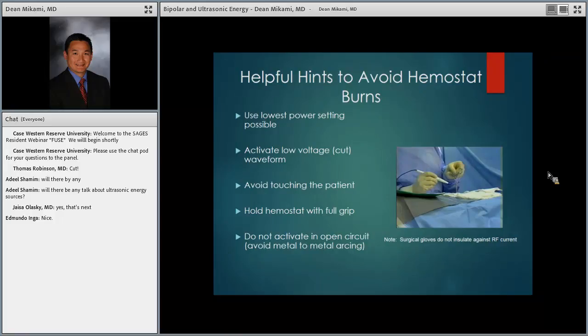And probably the most important thing is, do not do open circuit activation or open air activation. And what I mean is, when you have your assistant, you tell your assistant, okay, hit the hemostat with your active electrode, they press the cut button or coag button, and it's already pressed before it touches the hemostat. So what happens now? Your ESU can't sense the current that's going through or the voltage yet. It needs the circuit to be completed so it can modulate the amount of energy.